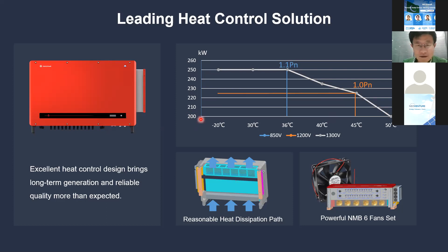Let's make an example. If you're using a new generation product from JA Solar, this kind of new generation PV panel, with GoodWe products the DC capacity can get more than 370 kilowatt, and the maximum AC output can get close to 250 kilowatt. So the DC AC ratio achieves 1.52. But compared with a traditional inverter, using the same PV panels matched to the subarray, the DC AC ratio is much less than GoodWe's.